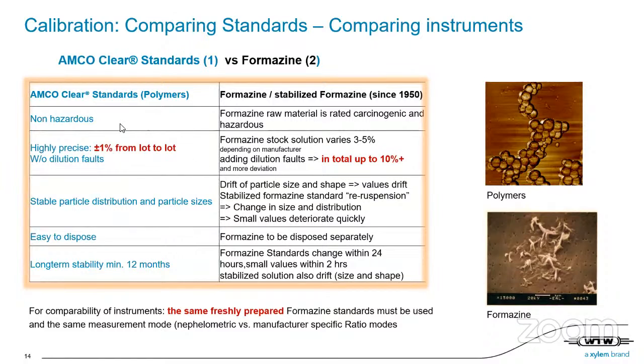drifting. The modern calibration, and we always talk, to remind you, about particle images. So we have differently shaped particles, if you think about a sand cone on the beach, if you think about a flake from the wastewater process after cleaning, if you think environmentally about some algae flakes. So actually we do have different forms and sizes, and polymer standards, it's not only AMCO Clear, there are others as well. So it's microspheres. And actually this is a defined bead. This is a defined composition. So smaller particles, bigger particles, different shapes, and each of these, they are non-hazardous as well.